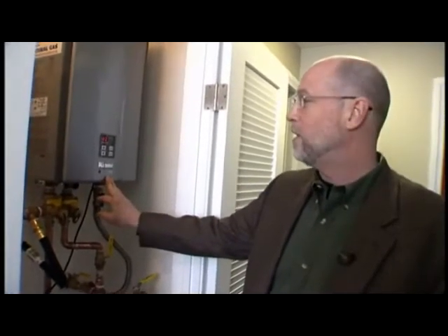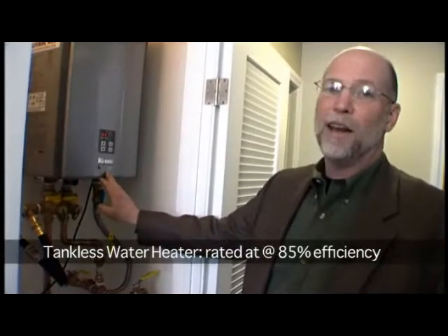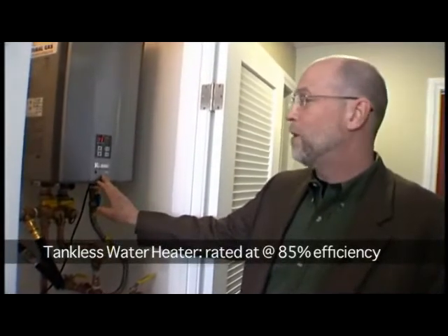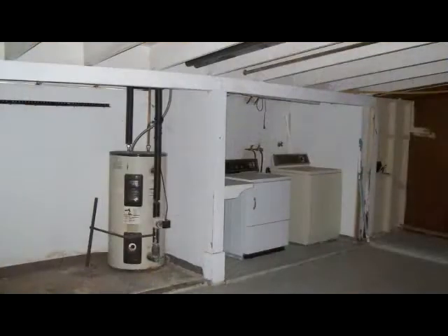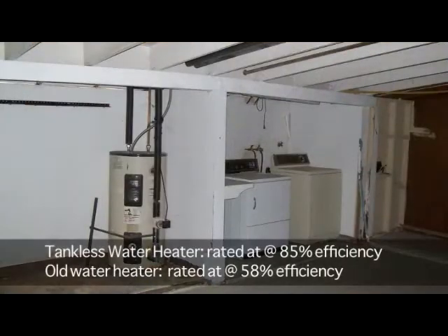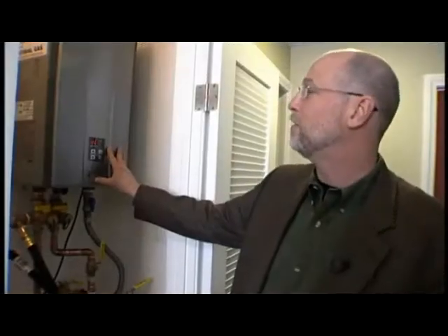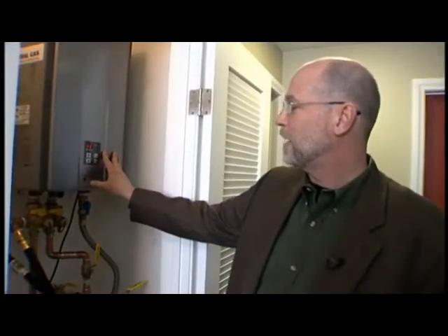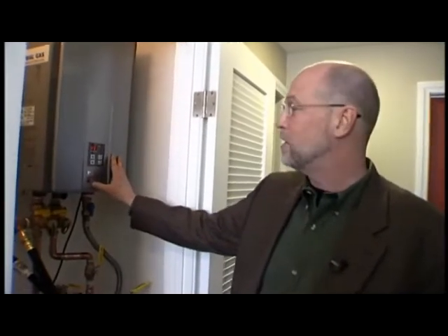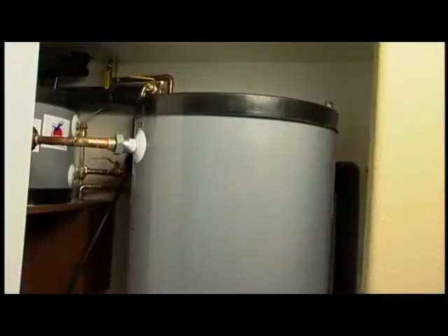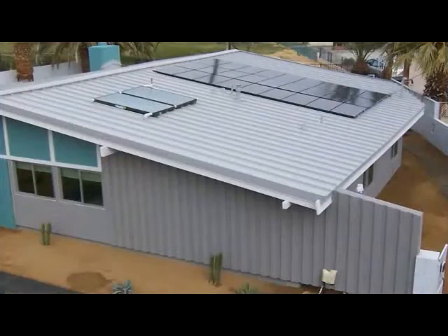This tankless water heater is rated at about 85% efficiency. Compare that to the tank that was here, which was rated at about 58% efficiency. So we had an increase of about 30% just by the installation of this modulating gas tankless water heater. Our strategy does not end here, however, because this is hooked up to a solar preheat system. That preheat is a 80-gallon storage tank with 2 solar panels mounted on the roof.